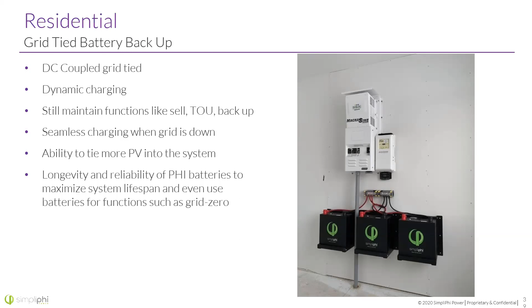We've talked about generators. Why does it make sense to have a battery in place of a diesel generator? Or even more, how can we add a battery, a controller, an inverter, and a PV array and still have a generator on site? Well, we can cut our diesel use by 50 to 70% just by adding storage. Add PV and you offset even more. As far as ROI over time, and with maintenance savings as Jake mentioned, it does actually save costs in the end.